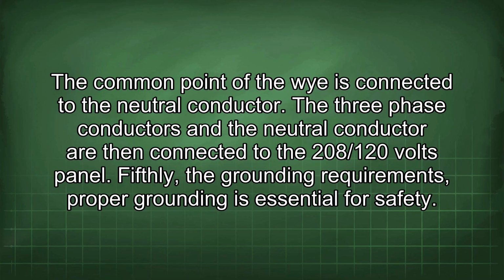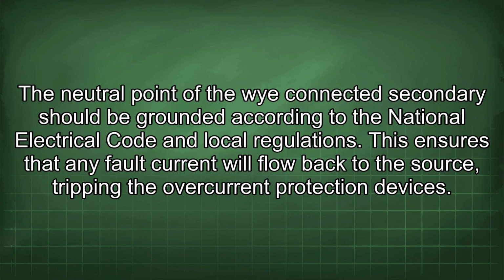The three-phase conductors and the neutral conductor are then connected to the 208/120 volts panel. Fifthly, the grounding requirements. Proper grounding is essential for safety. The neutral point of the Y-connected secondary should be grounded according to the National Electrical Code and local regulations. This ensures that any fault current will flow back to the source, tripping the overcurrent protection devices.